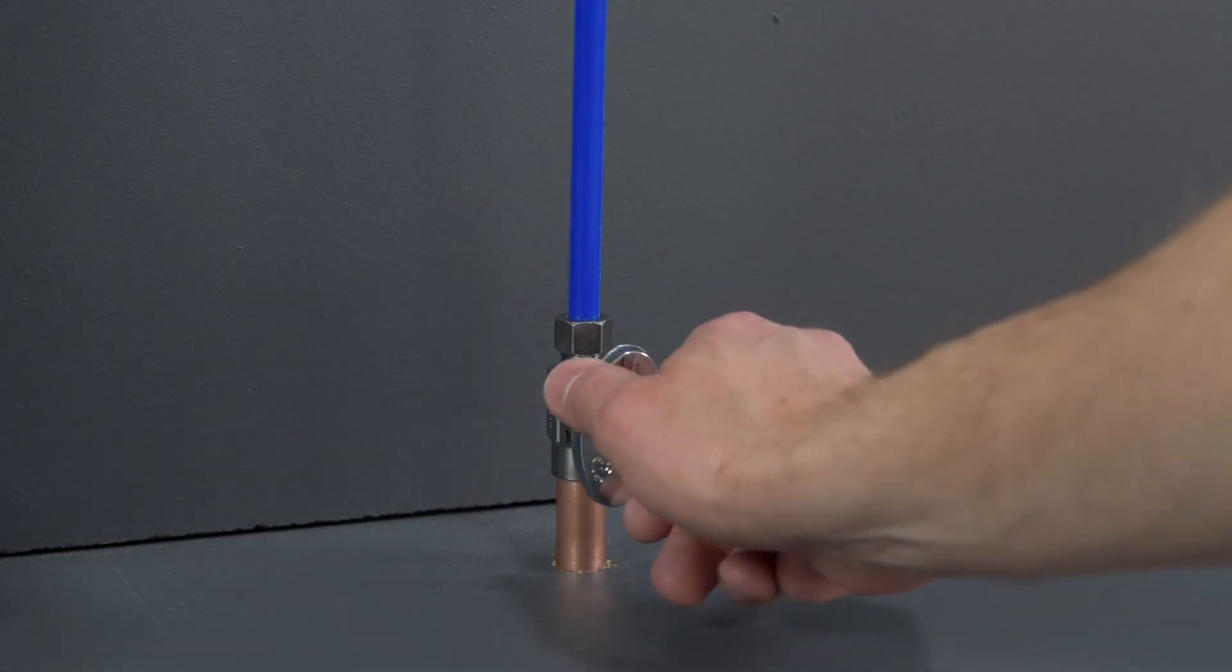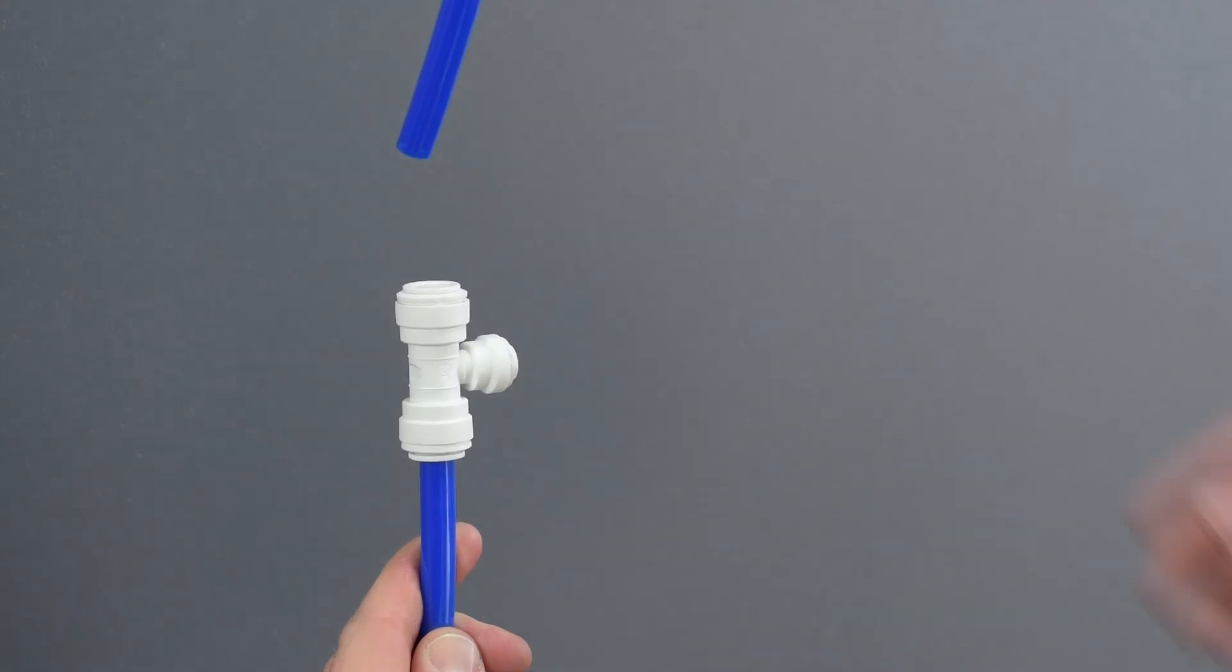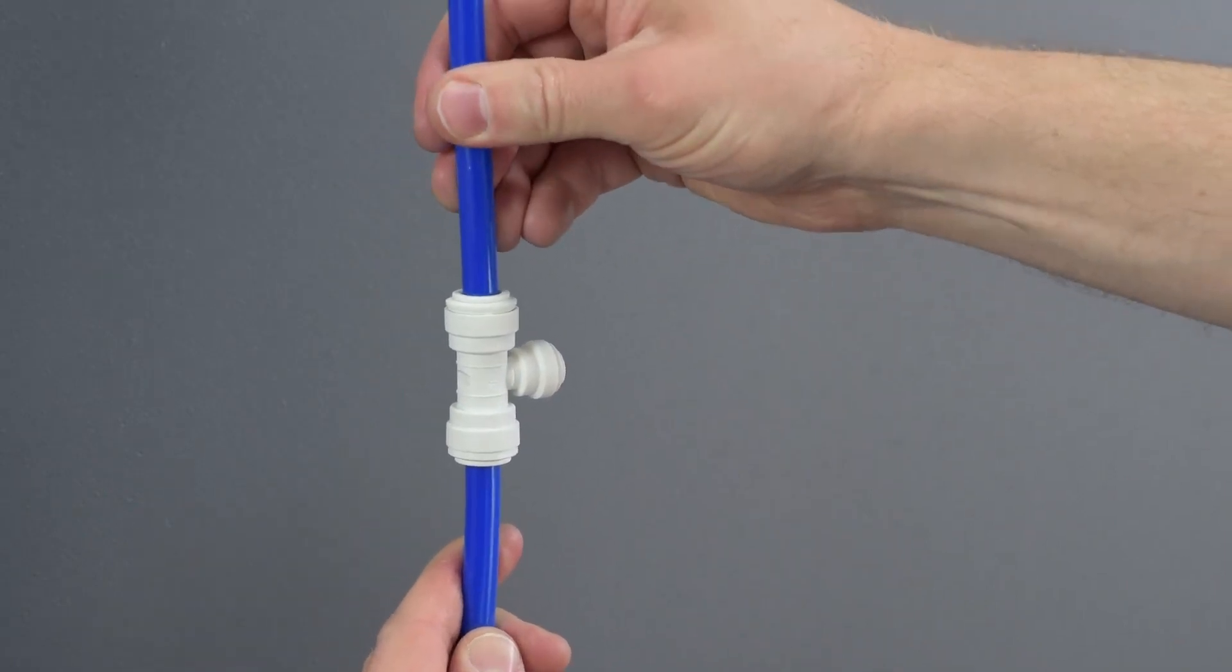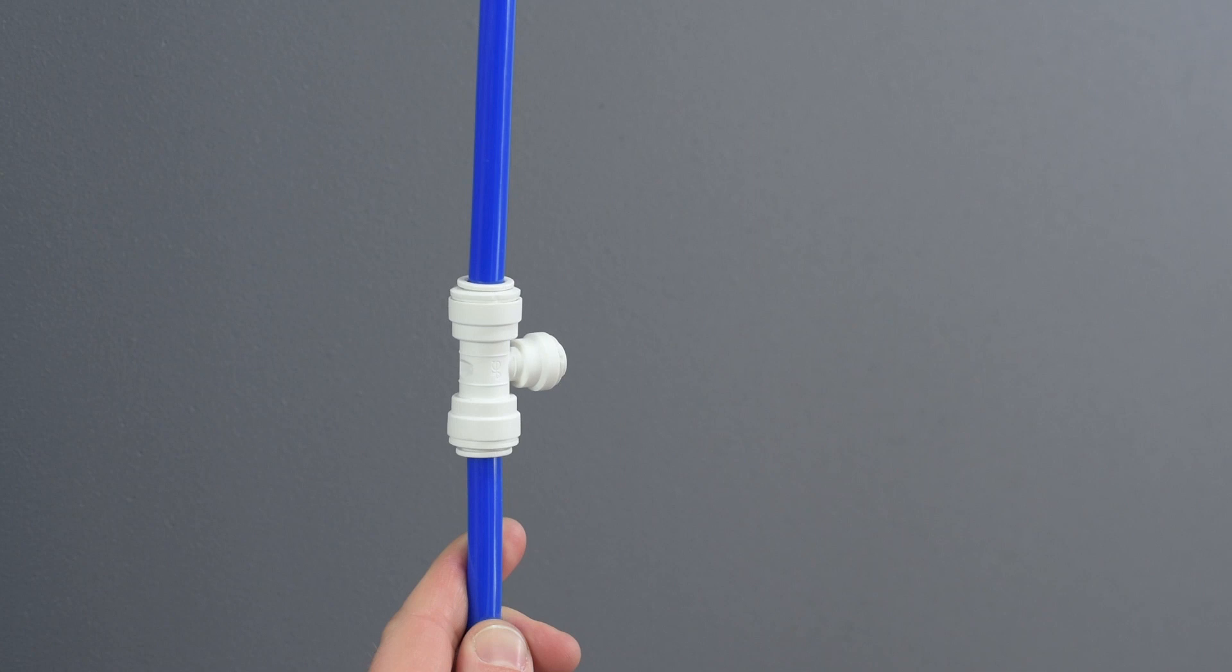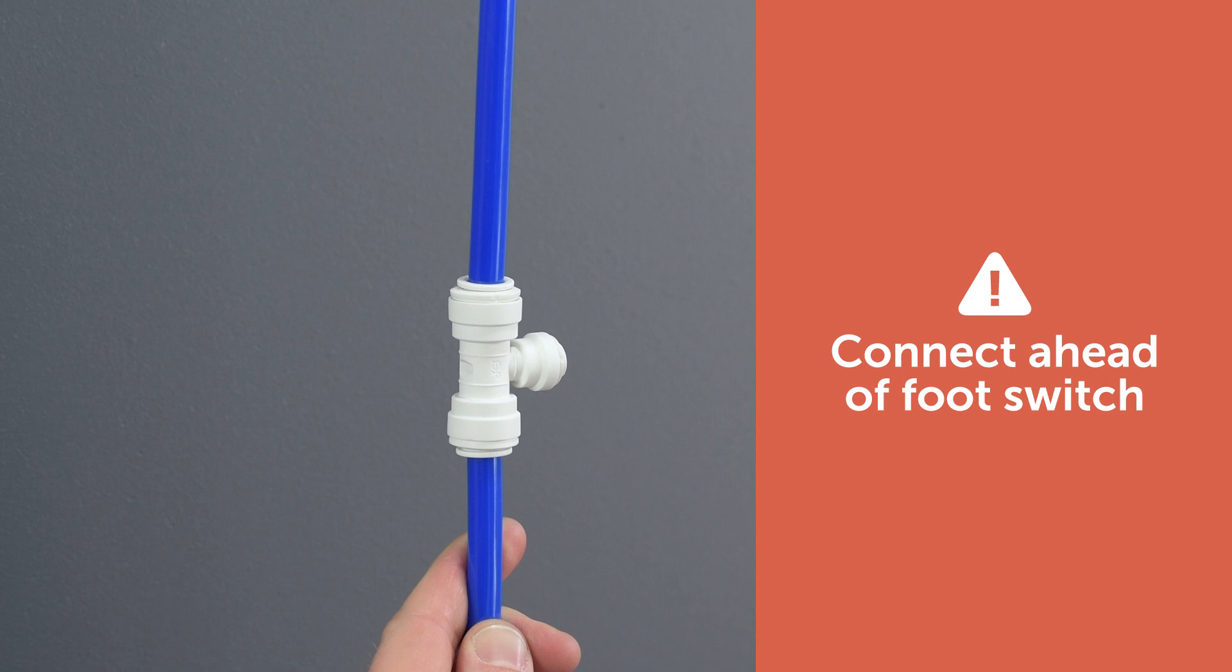First, turn off the water supply. Tap the cold water line with a T, valve, or compression valve so the quarter inch polyurethane tubing can be connected. Be sure to connect to the cold water supply ahead of any foot switch that might be present for uninterrupted water supply.